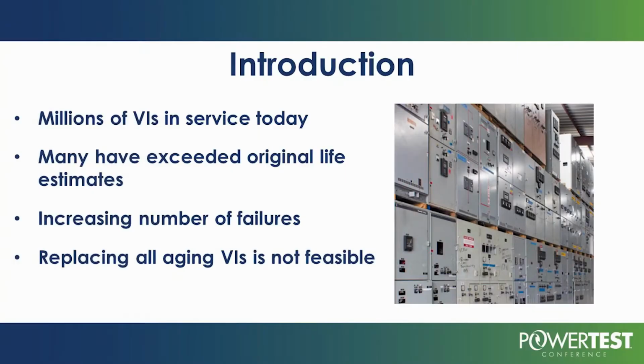Why is conditioning important? Because replacing them all is unfeasible. You get to a position where your fleet is 40 years old, you're going to start to have failures. From a reliability standpoint, you'd like to replace them all, but you can't. The downtime, the cost, the labor, the potential for damage is too high. So the conditioning process is the one tool you will have to be able to keep your entire fleet healthy and to make it last longer and extend the usable life of this equipment. And that's what we all want to do.